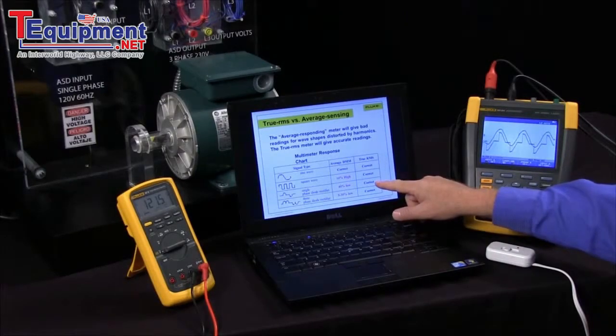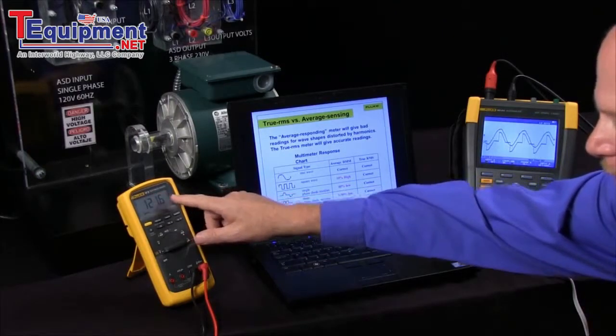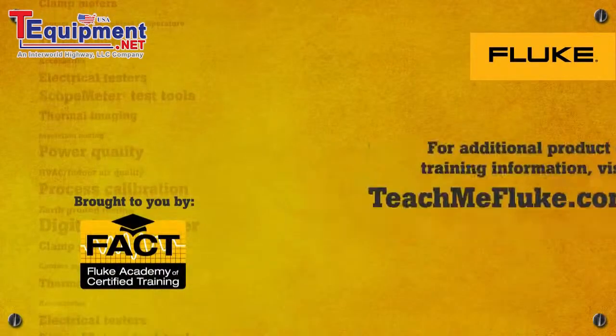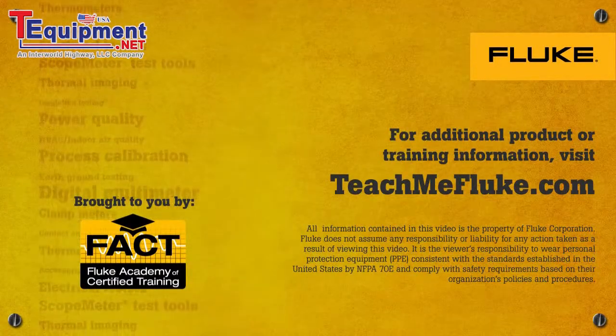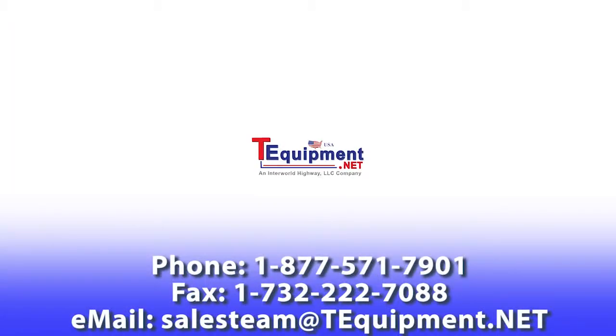This could cause you a lot of problems if you have a breaker that's popping intermittently and you measure it with an average responding meter. You're reading 13 amps on a 15-amp breaker, you say, okay, well that's not the problem. If you take a true RMS meter, you might read 18 amps on that 15-amp breaker, and then you're saying, I wonder why it's not popping all the time. So in today's world of electronic loads, it's very important to have a true RMS multimeter or a true RMS clamp meter to get the correct reading on current.